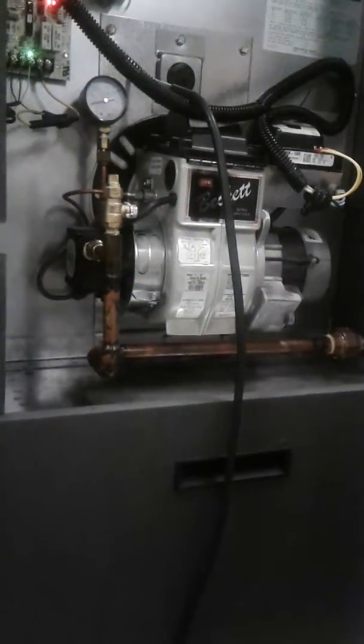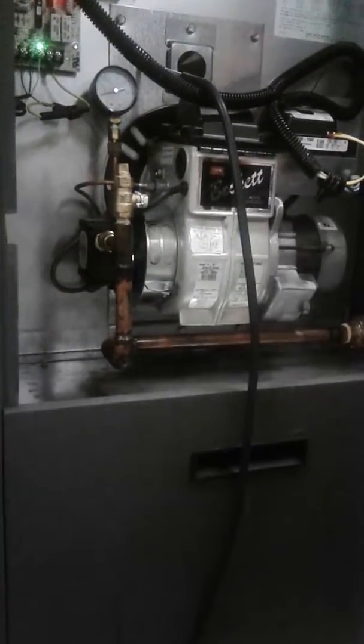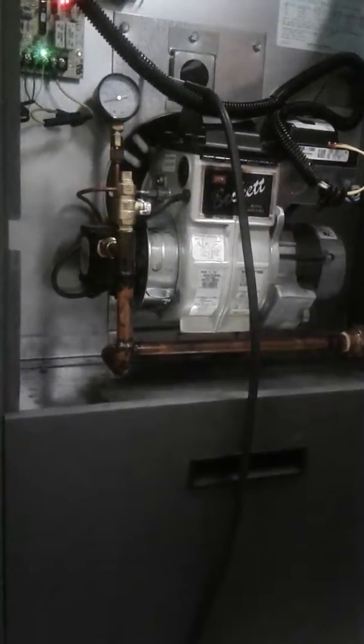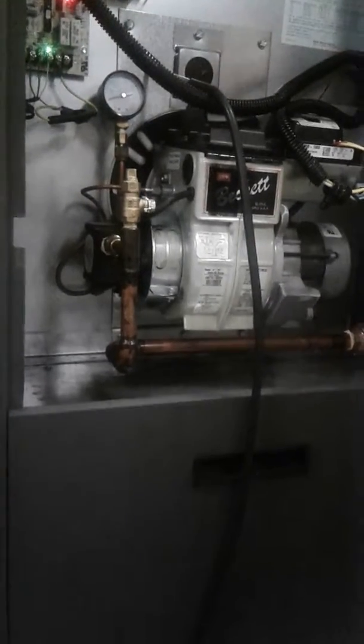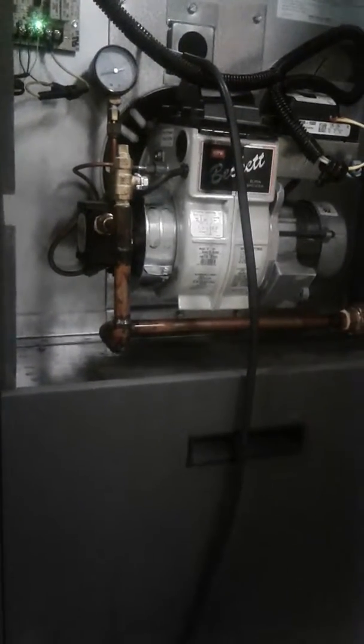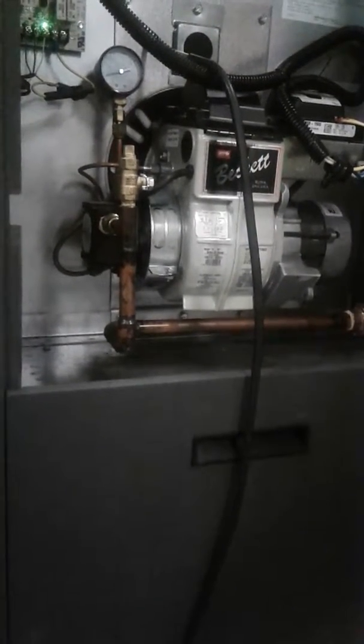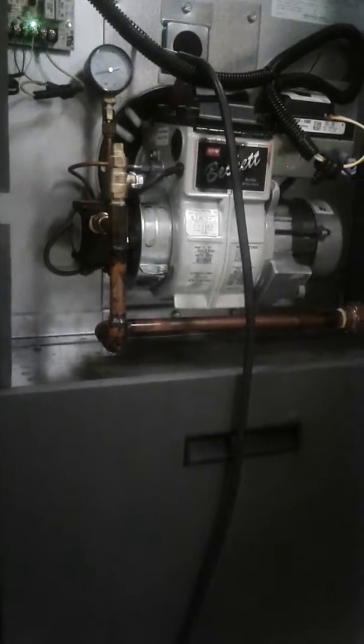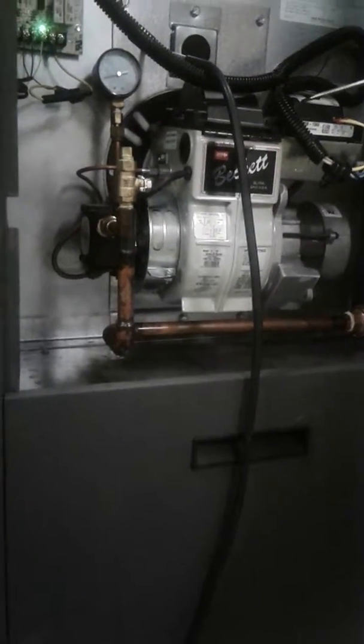Wipe up the oil while it's resetting, and it'll restart itself. So right now it's resetting. It's recycling right now. Just the blower is on, cooling down the heat exchanger. Once it gets down to a certain lower temperature and purges itself, this will stop flashing and the unit will start up again. The recycling start up.